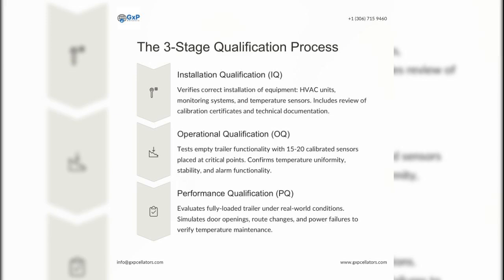The qualification process for trailers involves 3 stages: installation qualification, IQ, operational qualification, OQ, and performance qualification, PQ. IQ verifies correct installation of equipment like HVAC units and temperature sensors. OQ tests empty trailer functionality with calibrated sensors to ensure uniformity and stability. PQ evaluates fully loaded trailers under real-world conditions, simulating door openings, route changes, and power failures to verify temperature maintenance.